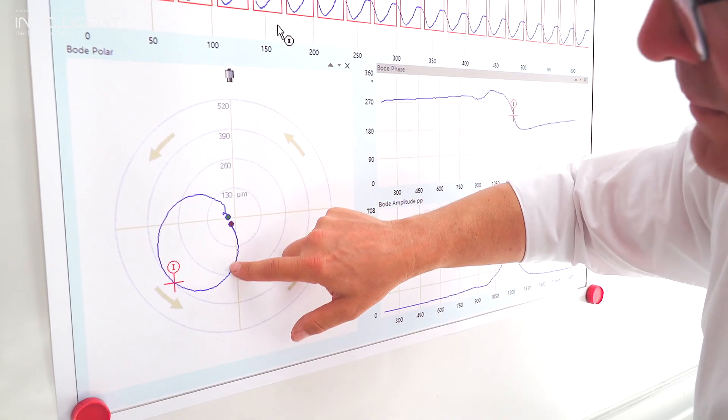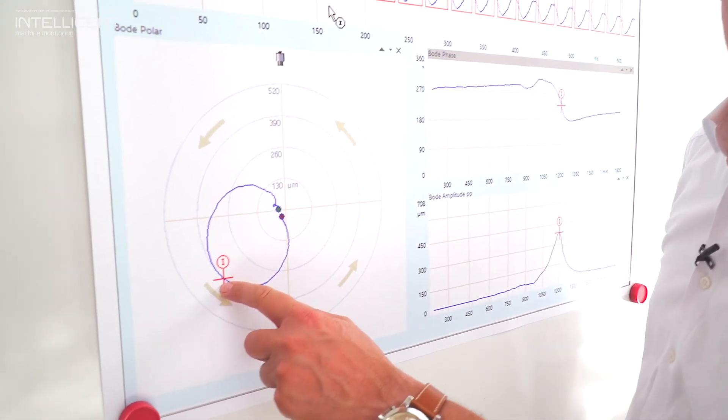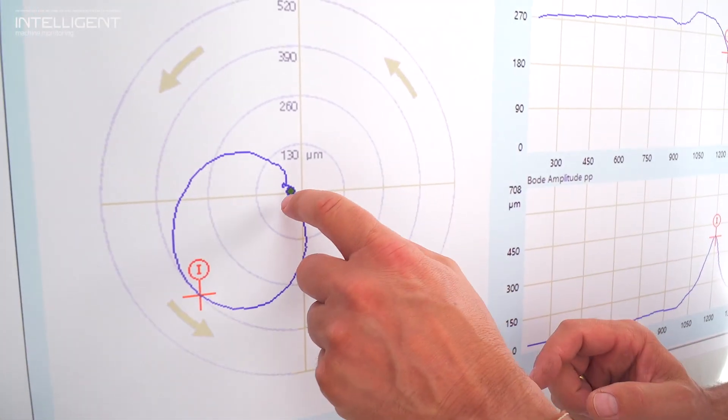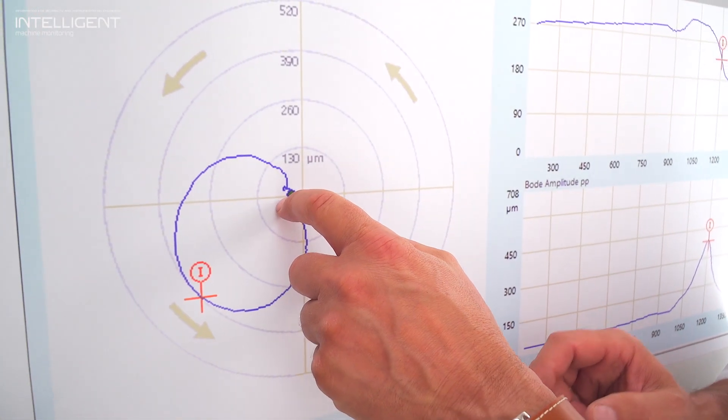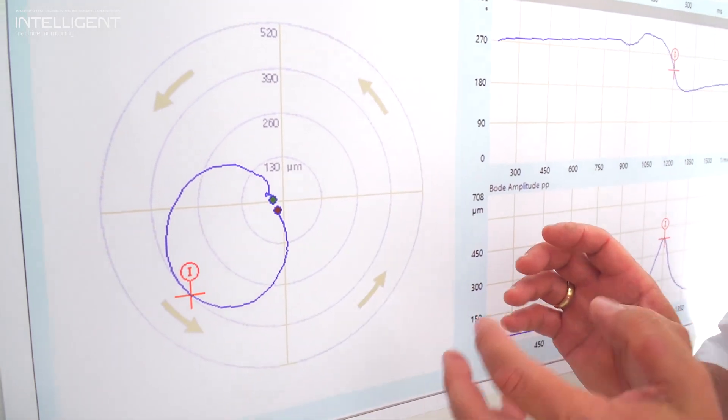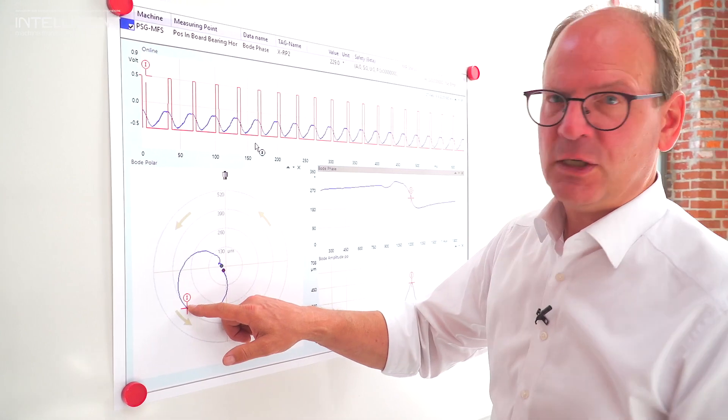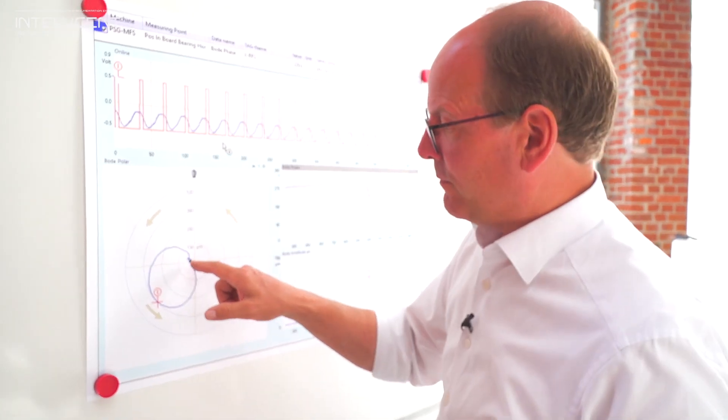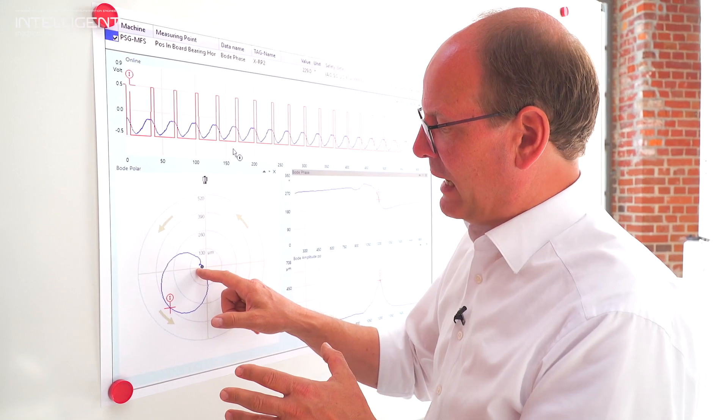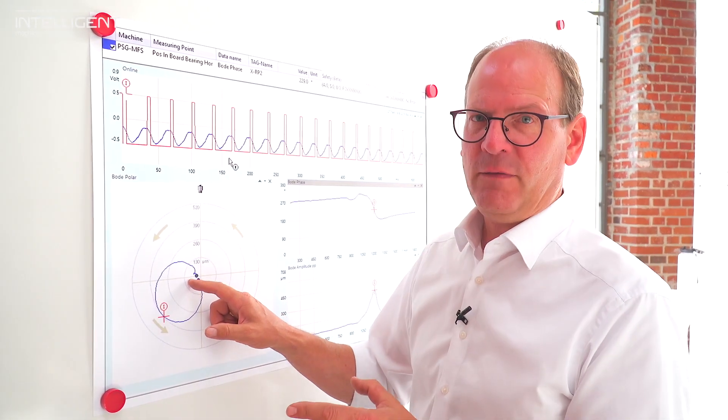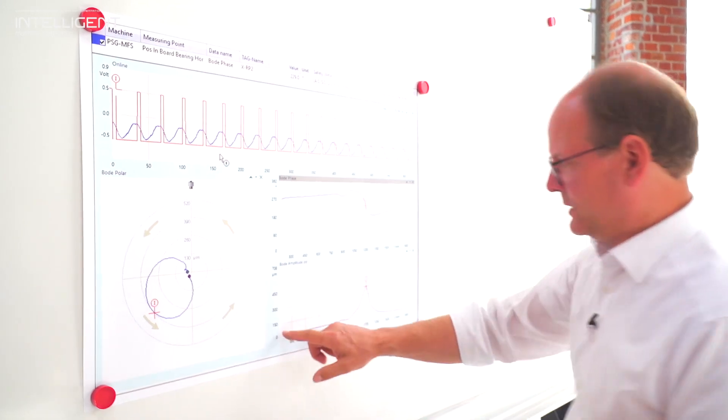Then we will reach here. This is a critical speed. That means when the machine starts we have the heavy spot and the high spot at the same position. When we reach the critical speed the heavy spot is always at the same point, but the high spot will be completely direct opposite to the heavy spot. And that is what we see here.